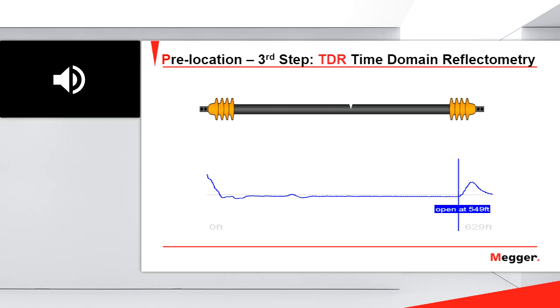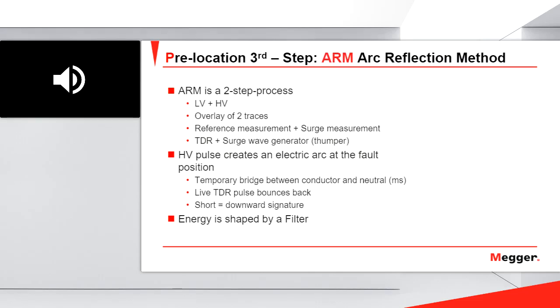What I need to do is send a high voltage pulse, and this is what I will do in the next step, in the arc reflection method. But why is this first trace important? Because this first trace shows me where my cable begins and where my cable ends. For that reason, this first step with the TDR is very important. So let's now find the fault in this pinhole fault. In this case, as I said, I need to combine the TDR and the arc reflection method. What the equipment will do is overlay two traces, the low voltage trace and the high voltage trace. Let me explain this in the next slide.